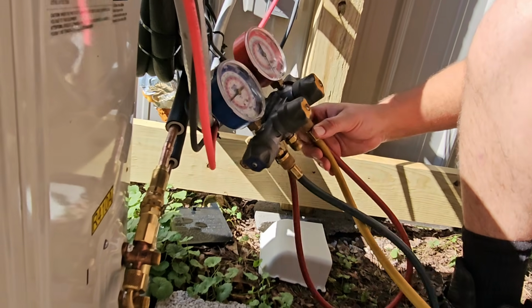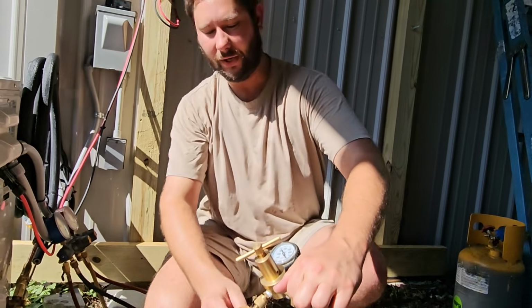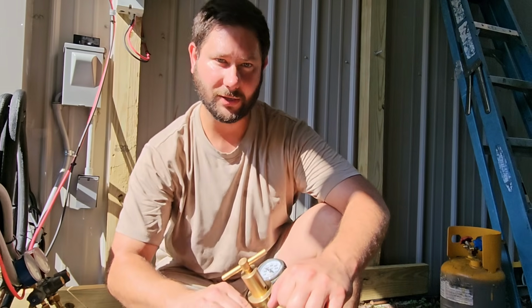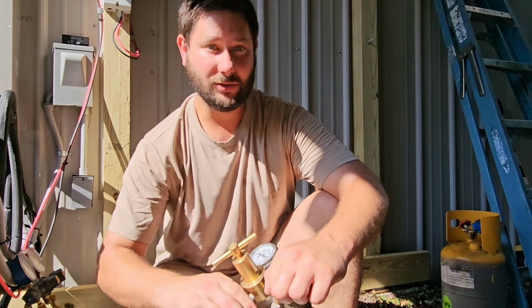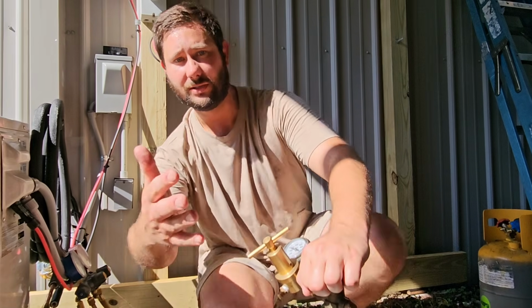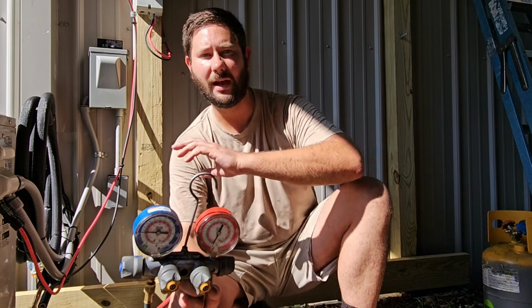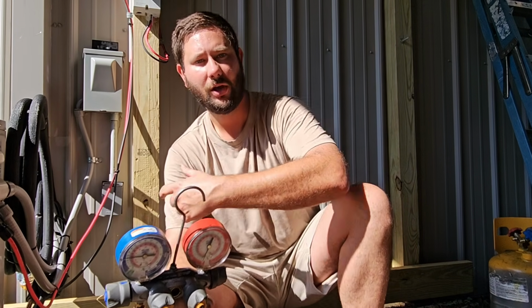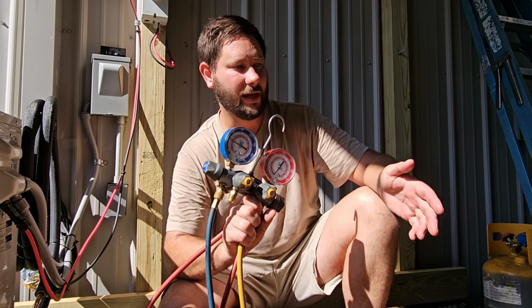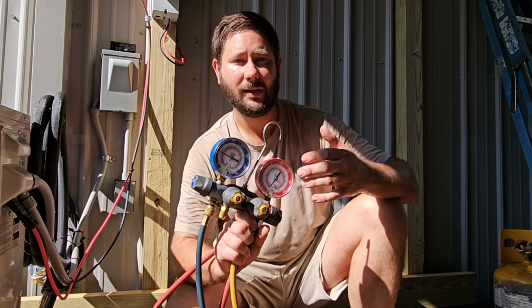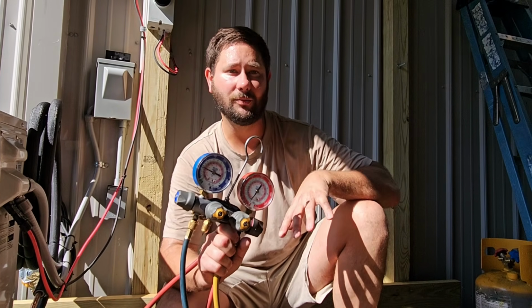Now I'm not going to put a bunch of pressure in here because I'm not doing a pressure test. I'm just doing this for learning purposes, to teach you. If you're doing a nitrogen pressure test and you've got flare fittings and you're doing a soak test where you spray those fittings, then you may need to pressure test with upwards of 500 psig. I'm not doing a pressure test. I'm just using the nitrogen so that I get a good vacuum. And the nitrogen is going to help me to remove the moisture and non-condensables.